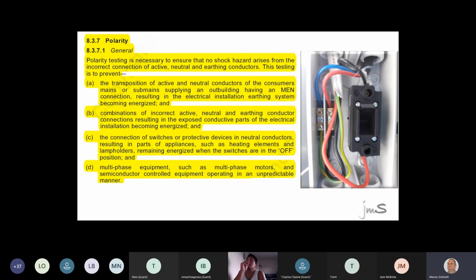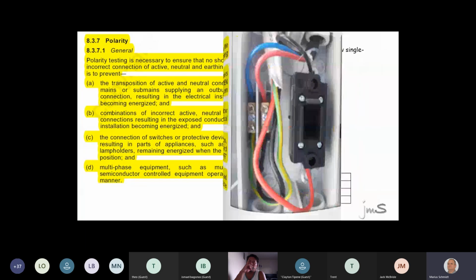Right, guys? And the last thing is, if I give you a multi-phase system, it's very important to know that red is red is red, white is white is white, blue is blue is blue. In other words, the phase rotation is the same. Have you guys ever heard about phase rotation? You know, when you take a little motor, it's going to go clockwise or anti-clockwise. Now, you test the direction in the beginning, switchboard, and further down. I'll show you this now.